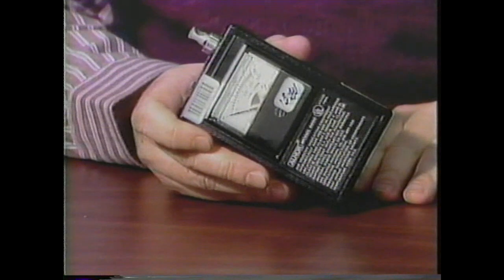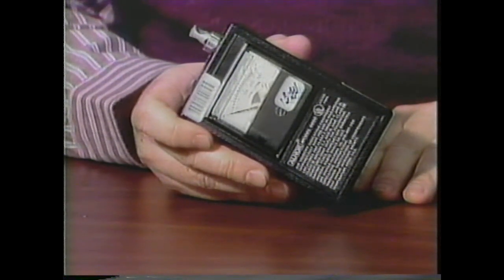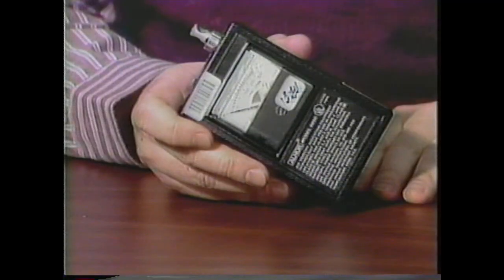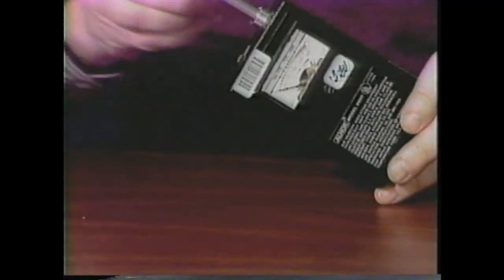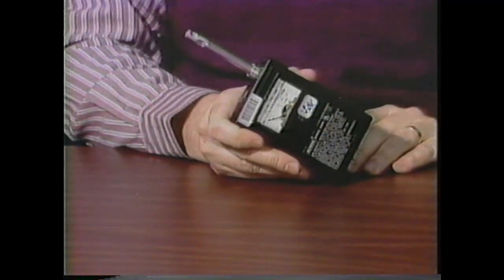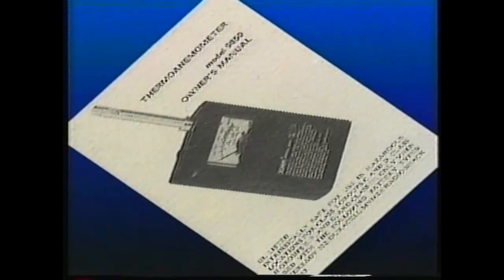The first type of velometer I'm going to describe is the Alnor thermal anemometer model 9850, more commonly referred to as the pocket hot wire velometer. It is a battery-operated, direct reading device capable of measuring air velocities of 20 to 2,000 feet per minute in two ranges. It has a retractable 3-inch probe used to measure the airflow. The owner's manual should be read before use. I'll be summarizing information found in the manual.